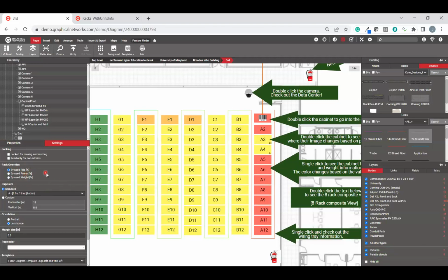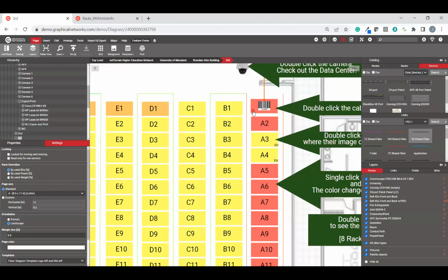And where is it getting this information to do the math? Well, it's what's rack mounted in the equipment. So in this cabinet, there's equipment, and that equipment has a certain size, rack units consumed, power, if there's a power associated with the object, passive device. And then, of course, the device can have weight. And those are usually manufacturer spec, but you can override that.